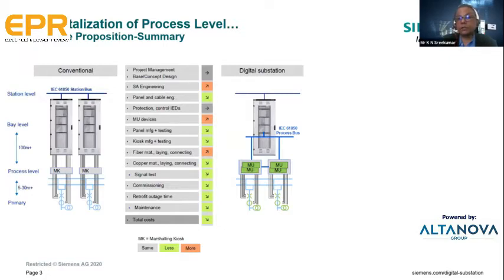A lot of kilometers of copper cable is consumed in these connections. Then you connect the process level from marshalling kiosk to bay level devices like relays and BCUs, typically in the 100-meter range, though exact lengths depend on substation construction. Bay level to station level, especially for transmission substations, already uses less copper, but up to bay level a lot of copper is still used.